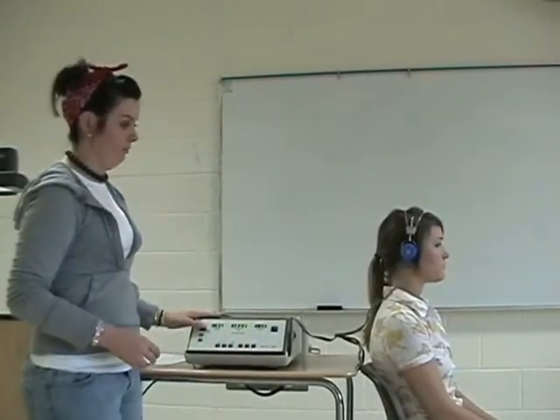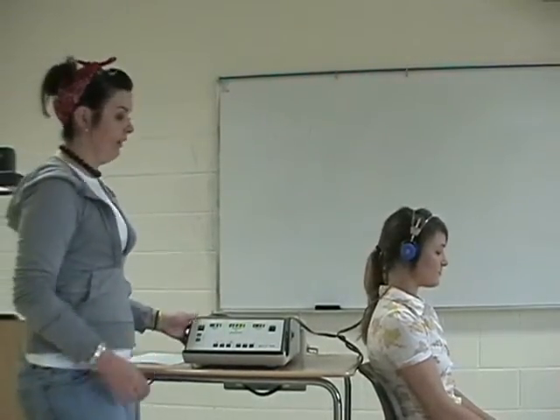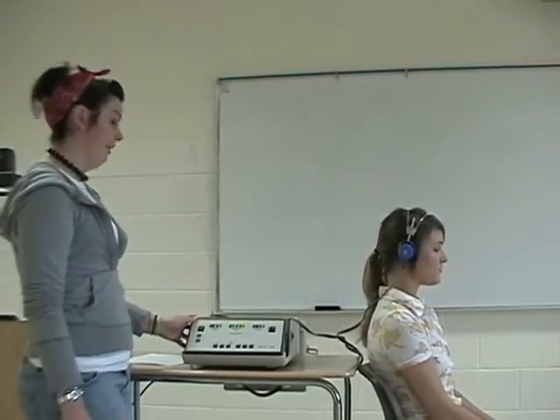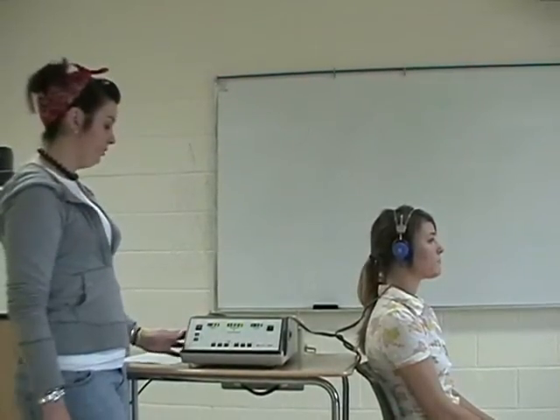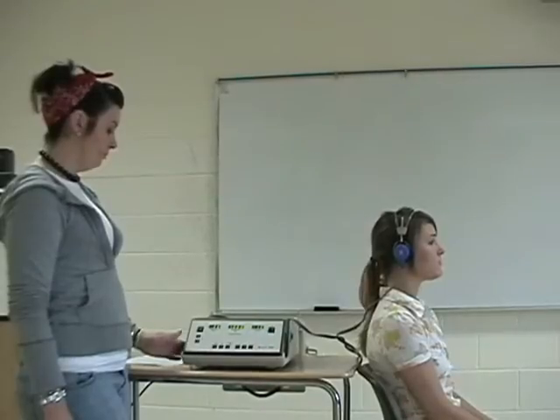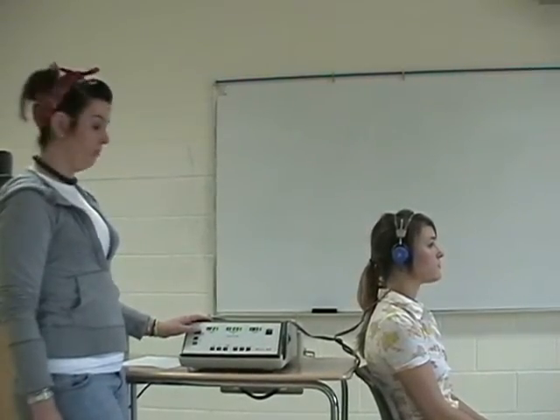You're going to hear this kind of tone. You will hear this kind of tone, but at a very quiet level. Please raise your hand when you hear it, even if it's very quiet.